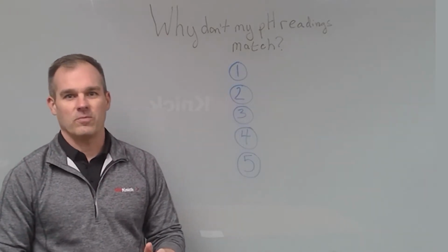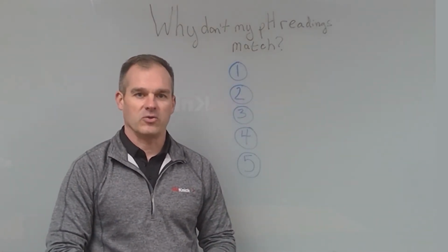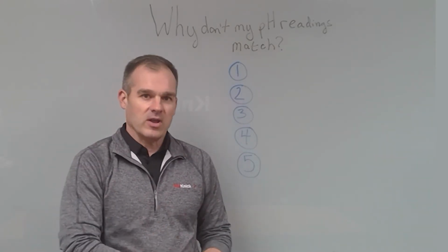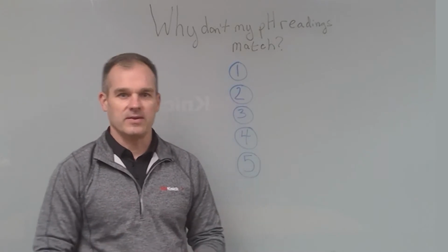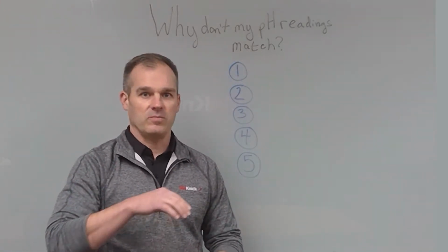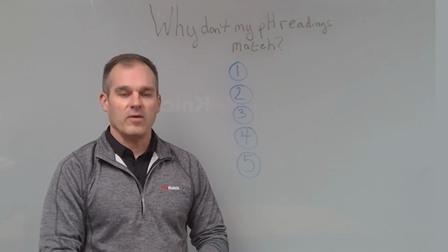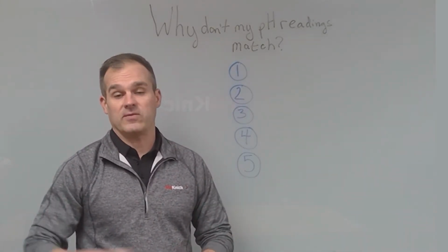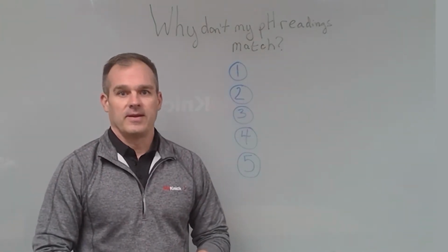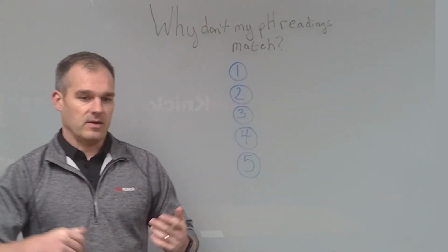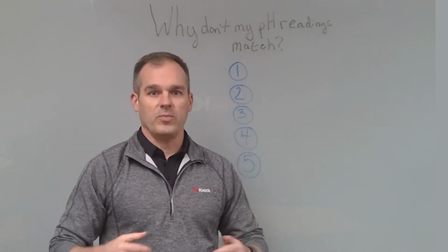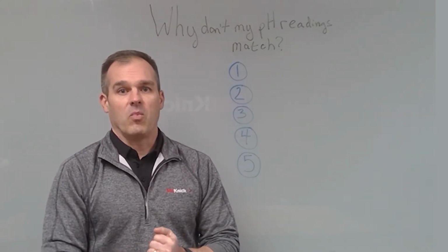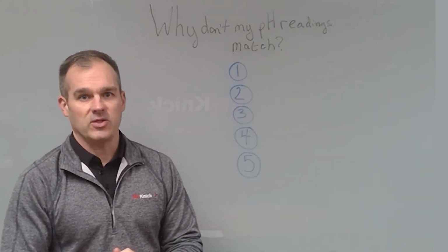Have you ever asked or been asked why your inline pH measurement doesn't match your reference measurement? When I'm talking about reference measurement, that could be a redundant inline measurement, it could be a portable measurement, and more often than not, where people run into trouble is when they're comparing to a laboratory measurement that's done offline and usually at a different time. The objective of this video is to help you to troubleshoot why those measurements don't match so that you can have more confidence in your inline pH measurement.